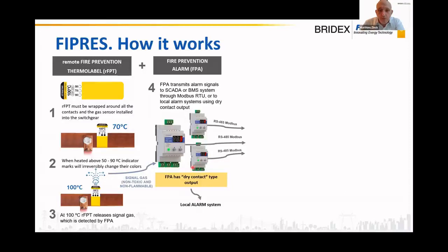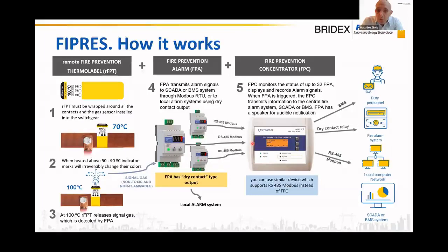So this electronic device has a dry contact output to send to an alarm in the form of a buzzer or a light, and also has RS-485 Modbus communication capabilities that can be sent either to a centralizer or concentrator, and that concentrator can be connected to your BMS, to your SCADA system, or to your alarm system. Or it can also be done directly. The device, the sensors, the FPA can be directly connected to the alarm system or the BMS via the RS-485. So that's the general principle of how it works.